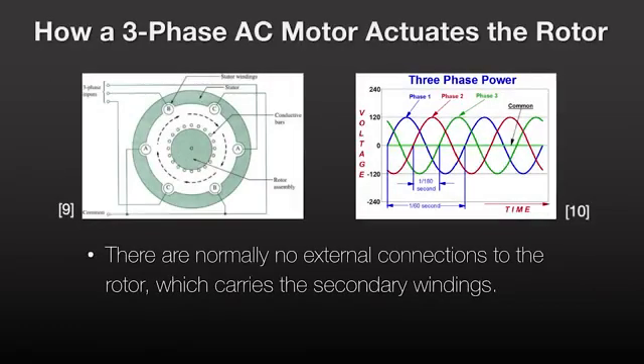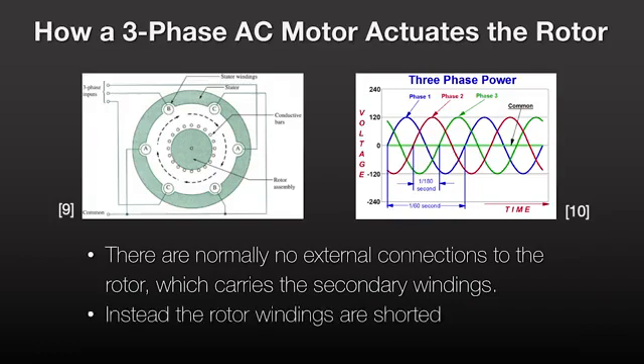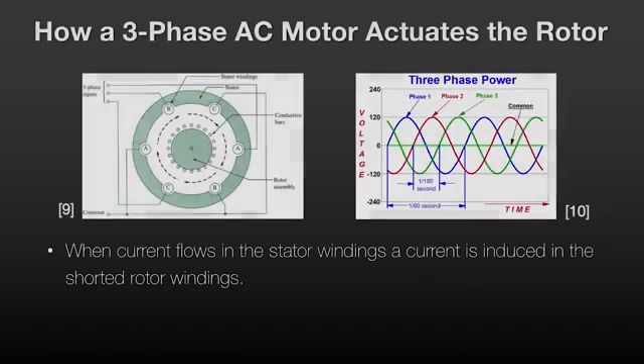There are no external connections to the rotor, which carries the secondary windings. The three-phase AC power inputs are connected directly to the stator pole pairs. All three phases of the AC power input have the same amplitude and frequency; they differ only in being 120 degrees out of phase with each other. The rotor windings are shorted together, a large electrical conductor rotating within a magnetic field. The AC induction motor gets its name from the fact that current is induced in the rotor windings by the magnetic field rotating around the stator.